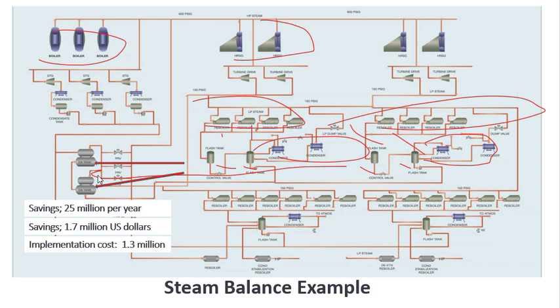First year savings, 25 million per year. I always put that in there, but the currency was rupiah. The real savings was 1.7 million US dollars converted. The implementation cost was 1.3 million. My point is they didn't know how to balance the system out until we did this balance and found that we could reroute piping back to the deaerator and achieve the savings. So it was very critical to have a steam balance.